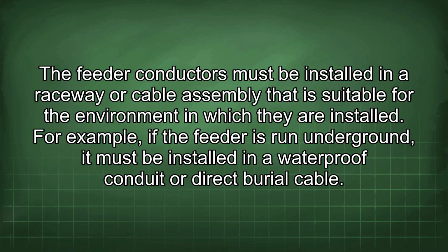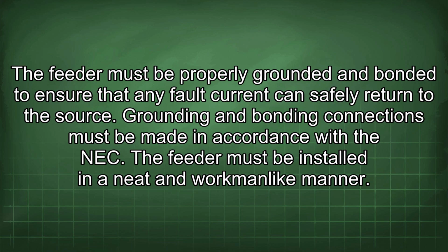The feeder conductors must be installed in a raceway or cable assembly that is suitable for the environment in which they are installed. For example, if the feeder is run underground, it must be installed in a waterproof conduit or direct burial cable. The feeder must be properly grounded and bonded to ensure that any fault current can safely return to the source. Grounding and bonding connections must be made in accordance with the NEC.